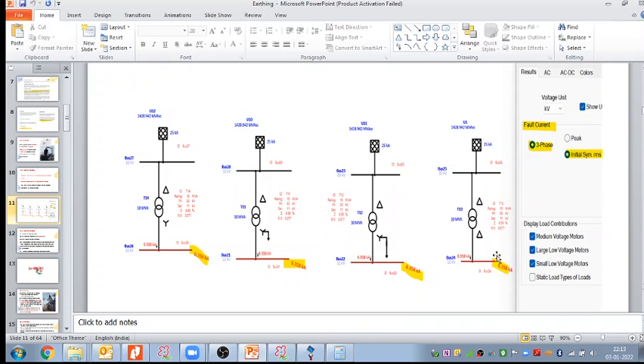Here I have taken four different examples, right? If I'm putting the NGR, what we understood from here is that I'm not limiting the three phase fault current. I hope this is clear. What I'm limiting, if I'm putting the NGR, is the line to ground fault current, not the three phase fault current. And that is the reason I have taken this NGR here. I hope this statement is clear now: the fault current type and the grounding system, their interrelation. Please let me know if this is clear. I can move to the next concept, because when we are coming to fault current earthing we should have total understanding. That's why I have taken this slide.